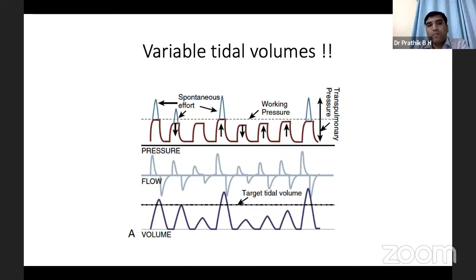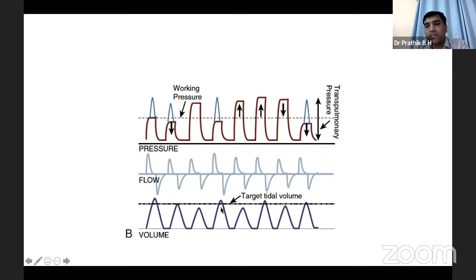But this problem has been overcome by the recent Draeger VN500 and Draeger Babylog 8000 ventilators, which have a separate algorithm for the spontaneous breaths of the baby and non-spontaneous breaths. For the spontaneous breaths, you can see here the pressure delivered is the same. For non-spontaneous breaths, that is only the ventilator-delivered breath, the working pressure is different. So this algorithm maintains the constant targeted tidal volume.